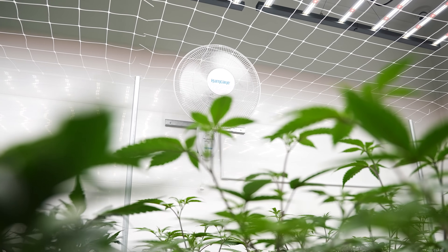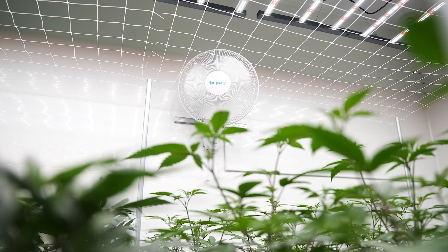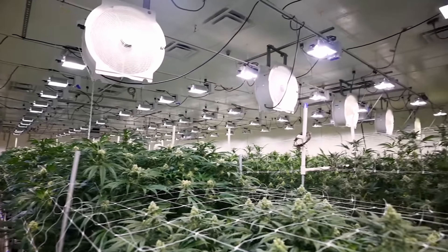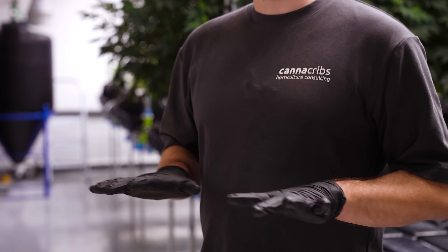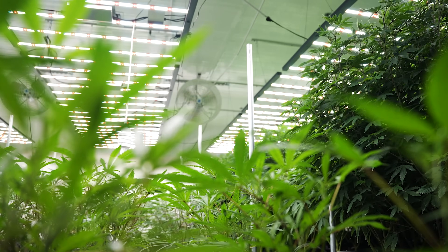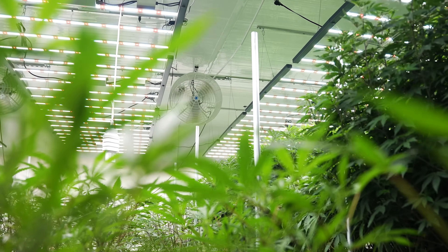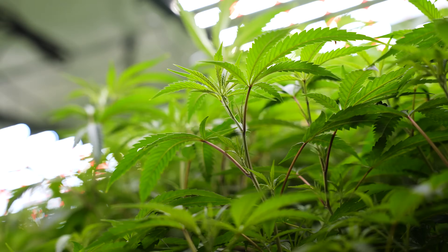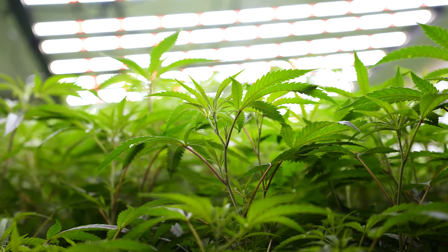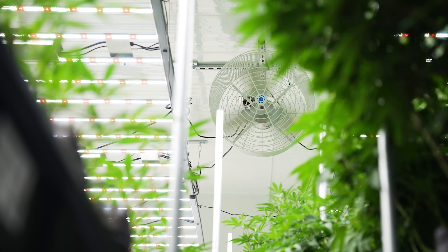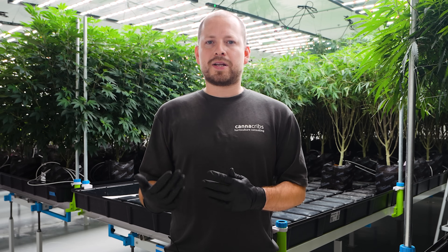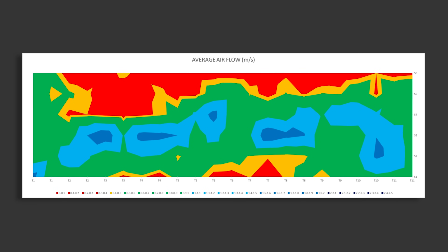In every facility that we walk through, we see a slightly different fan configuration. We may have oscillating fans or we may have fixed fans pointing a specific direction. What we like to see in a grow room is fans pointing a single direction so that it creates a laminar flow. This creates a constant flow of air over the top of the canopy, making it easier for the grower to manage the airflow. Oscillating fans could work, but the oscillation could create gusts of wind in different areas, causing points of non-uniformity.